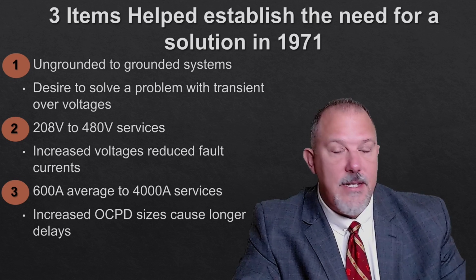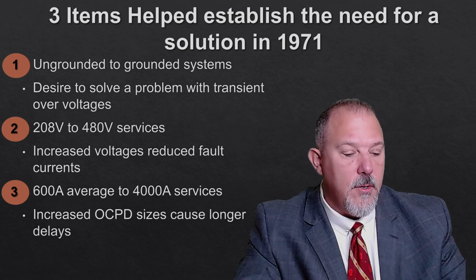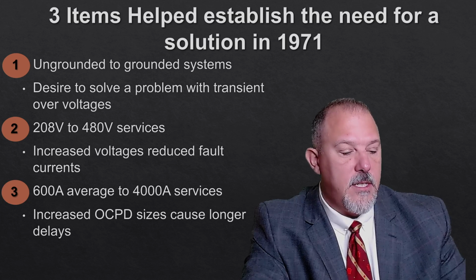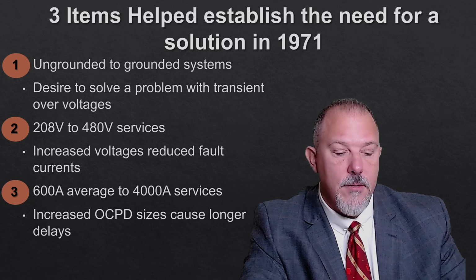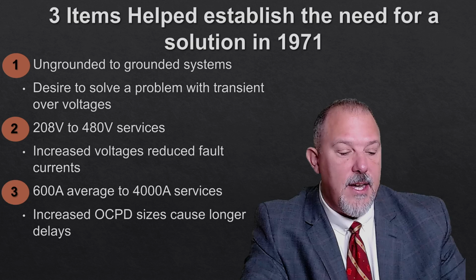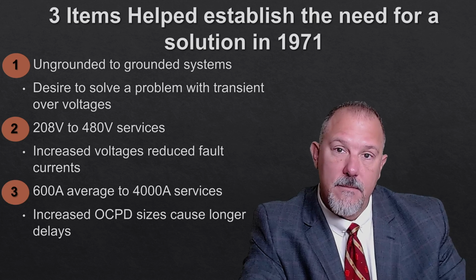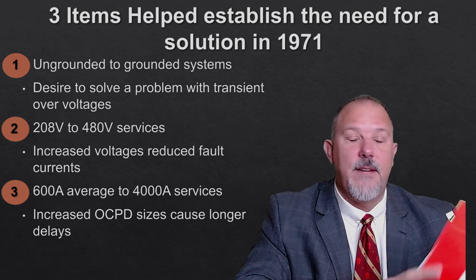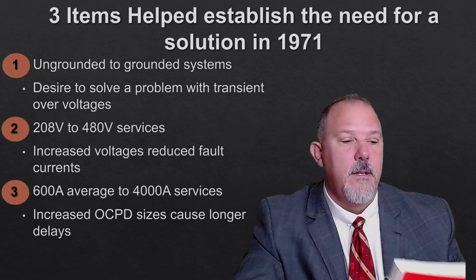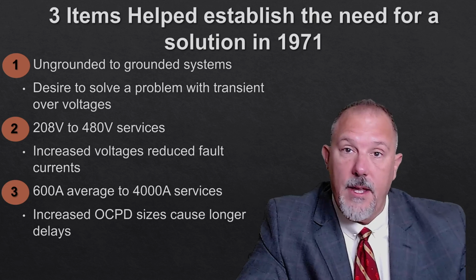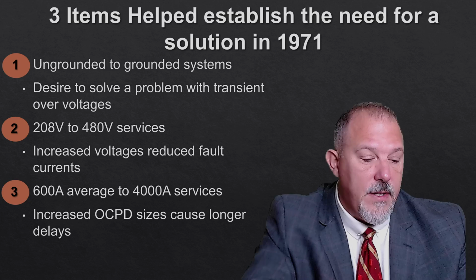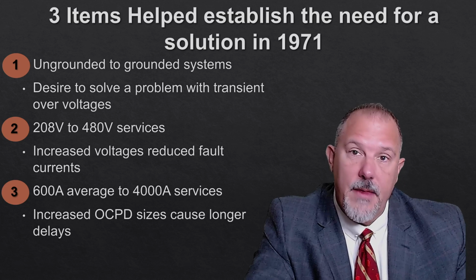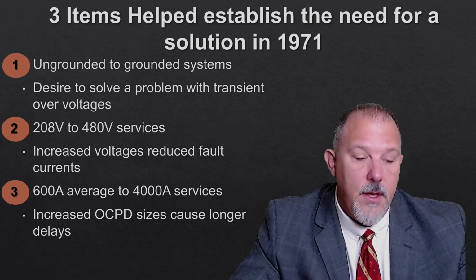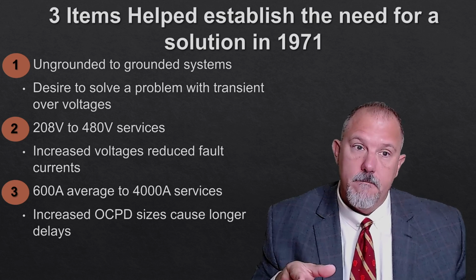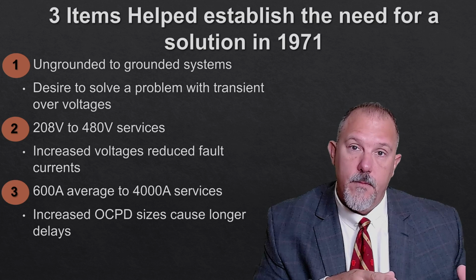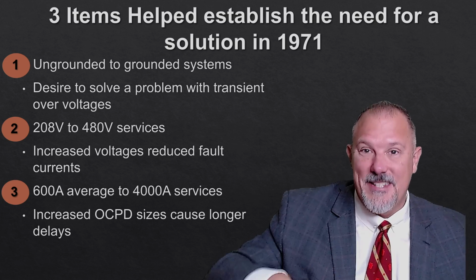During the past several years, at least 5 major cities have reported major electrical equipment damage, and in 2 instances, fatalities have occurred in which low fault currents have persisted for a sufficient time to cause very extensive damage. The 1971 substantiation for GFPE: arc flash events. These events took lives in various cities, and they noticed the trend. There are numerous IEEE papers, which we'll talk about, that documented the issues. And there was a lot of testing done in the 60s and 70s.